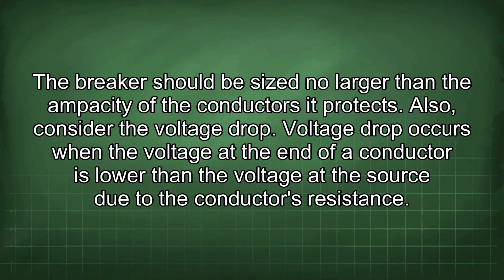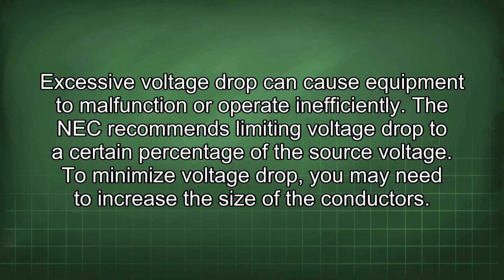Also, consider the voltage drop. Voltage drop occurs when the voltage at the end of a conductor is lower than the voltage at the source due to the conductor's resistance. Excessive voltage drop can cause equipment to malfunction or operate inefficiently. The NEC recommends limiting voltage drop to a certain percentage of the source voltage. To minimize voltage drop, you may need to increase the size of the conductors.